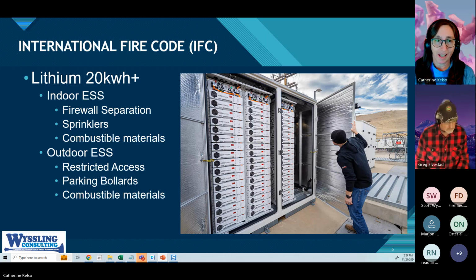Keep in mind the fire code applies to lithium battery systems over 20 kilowatt hours. Everyone thinks, this battery system is small, only 30 kilowatt hours, no big deal. But that's big enough to trigger International Fire Code jurisdiction, and you have to abide by all the rules in there, even though they seem excessive sometimes.